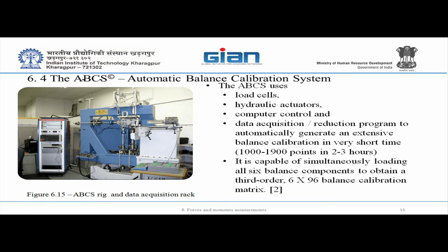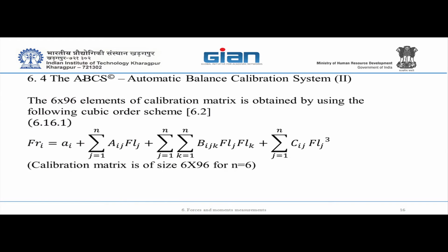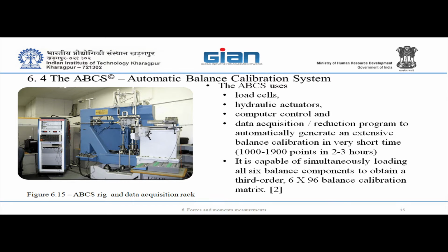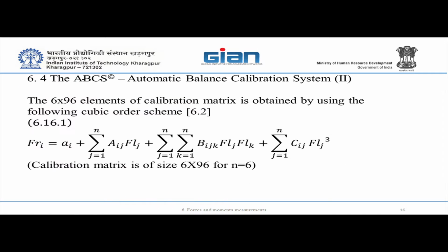Anyway, we'll get back to that. Here I have one point. The loading points previously were 1000 to 1900. So will the accuracy improve if we use more loading points than this 1900? I don't feel so. The more accuracy you gain is by retro calibration, as I was describing in answer to the professor.